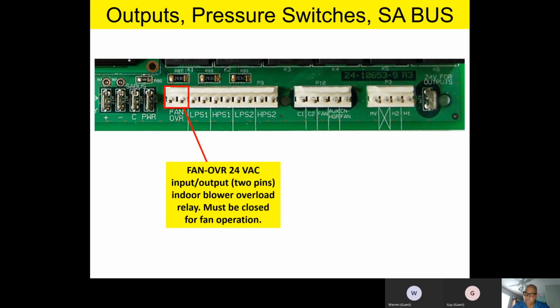Now this is a little field tip. This is very important, so make a note of this or write this down. This fan overload is a 24-volt input-output, and that has to be closed electrically in order for the indoor blower to work. So let's say, for instance, the contractor, it's on a Sunday, and he's out in the country, and he's working at a plant, and he goes to his truck, and he doesn't have an exact OEM replacement motor. But he's got a motor that's the right phase and the right rotation and the right RPM and the right horsepower and the right voltage on his truck. We'll say it's a rescue motor. But let's say that rescue motor does not have a fan overload on it, or those auxiliary contacts on the fan as a safety circuit.